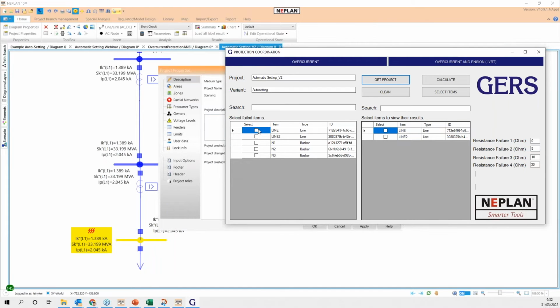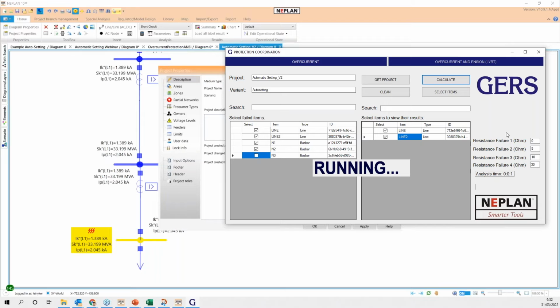And in that application, we are getting the different elements that we have in the project, and we can set for what elements we can get results and automate different fault locations and different resistance failures on the system. That means that using NEPLAN web services, I can provide automations, and we can see that just for this small sample, we have to run more than 100 simulations. So can you imagine how many simulations we need in more complex networks? In distribution networks with a lot of nodes and in transmission networks, the number of required simulations is too high. So I will continue illustrating the different applications with NEPLAN while this number of simulations finishes.